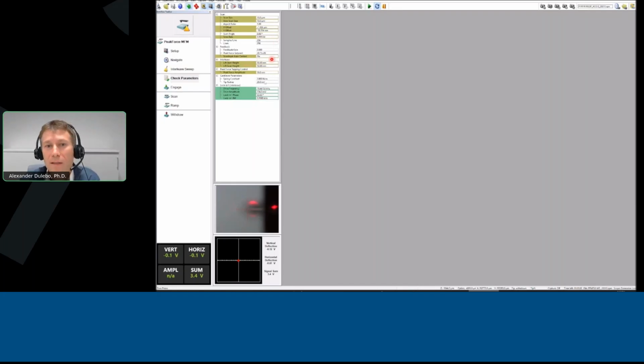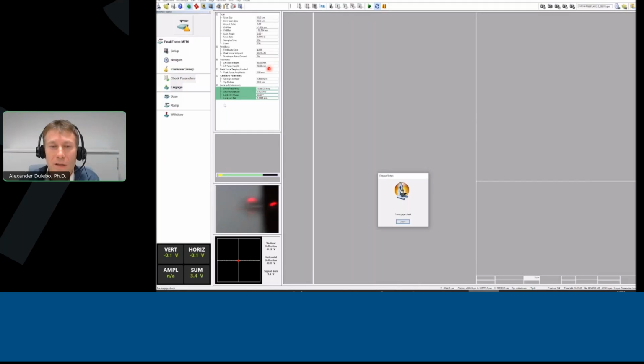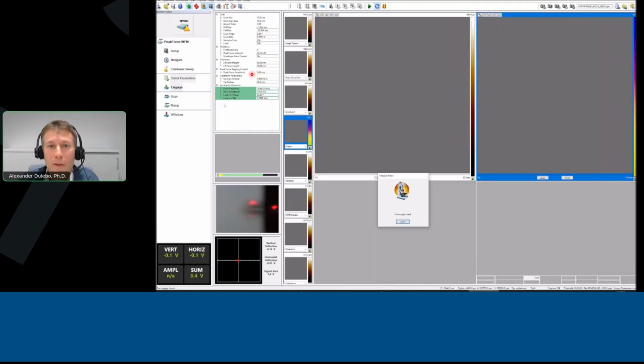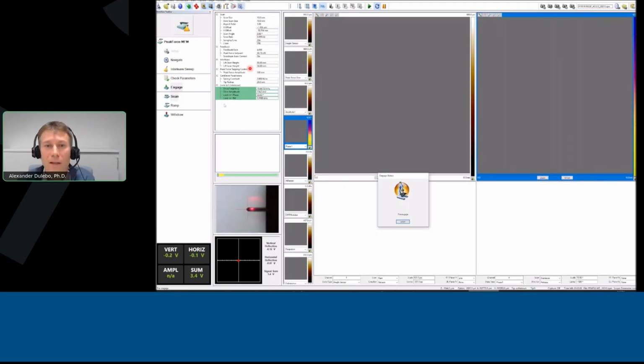My ScanAsyst control is fully on, so both force and set point will be automatically adjusted, and my PeakForce tapping amplitude will be at 50 nanometers, as well as lift height. So right now I'm approaching my sample of interest. The laser, of course, was already aligned.